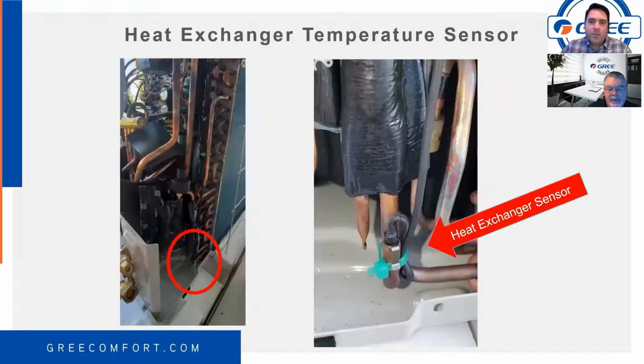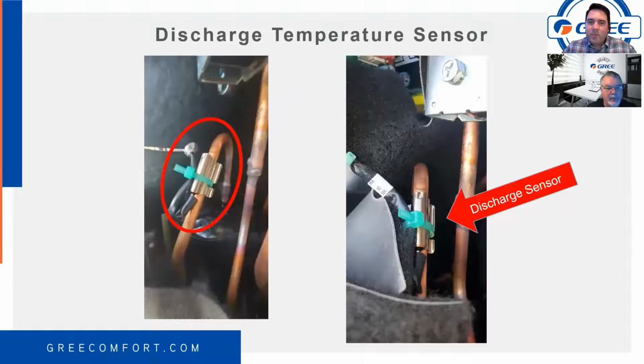Dryer vents. Yeah, dryer vent. Or a bush, or being too close to the house. If it's not able to draw the air across there, it could throw a reading. Then this is the condenser coil sensor, which senses the temperature right on the pipe, and then does calculations in the board to figure out what to do with the EEV and all the rest.